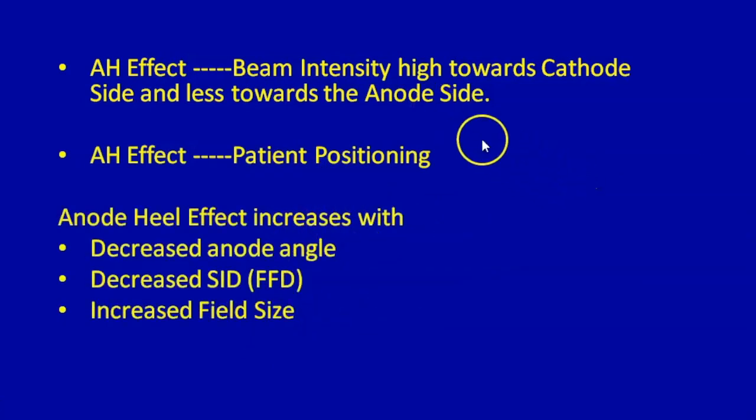Summarizing the anode heel effect, the beam intensity is high towards the cathode side and less intense towards the anode side. We can take advantage of anode heel effect and position the patient accordingly such that the more dense parts are placed towards the cathode side and the less dense parts are placed towards the anode side.